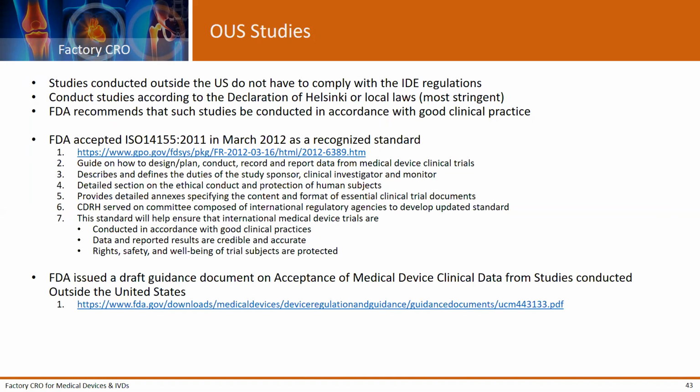One comment related to that, one of the companies that I worked for was doing a fairly large clinical study on a high-risk device. It was a combination product, and as they went through the study, because it's a high-risk study, they had some adverse events and some deaths. And those weren't unexpected. However, because each time that they had an adverse event, their protocol, because they outsourced the contract manufacturing of the device, their protocol was to have the device sent to the contract manufacturer to do an investigation, because they felt the contract manufacturer would do a better job of investigating why the device failed.